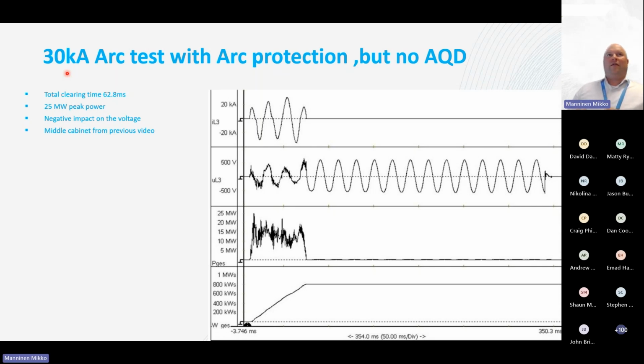And the biggest current levels I have seen in LV boards have been 300 kiloamps. So the trend is there because of a lot of drive panels, microgrids, capacitors, big capacitance, or huge capacitors in the bus bars, DC network, DC grid, and it is getting these low voltage panels closer, already easily 100 kiloamps, but even higher.